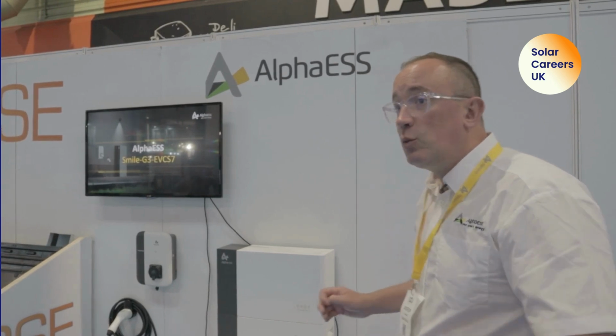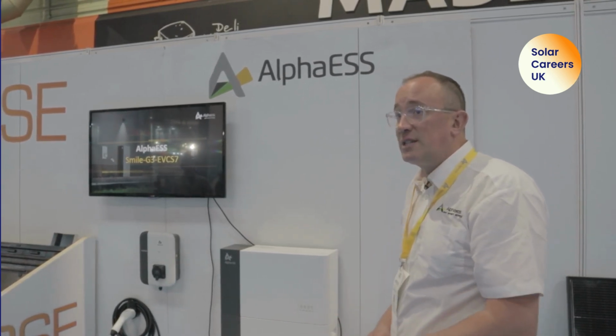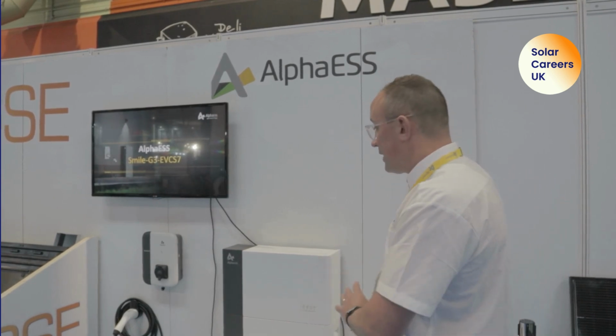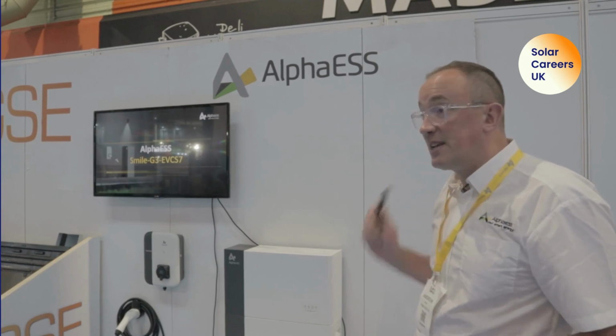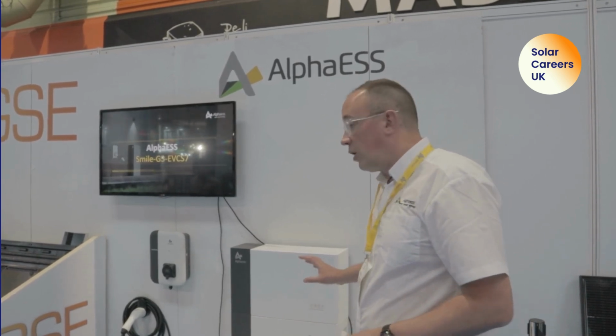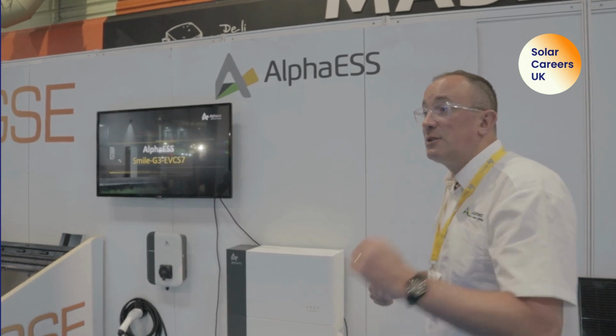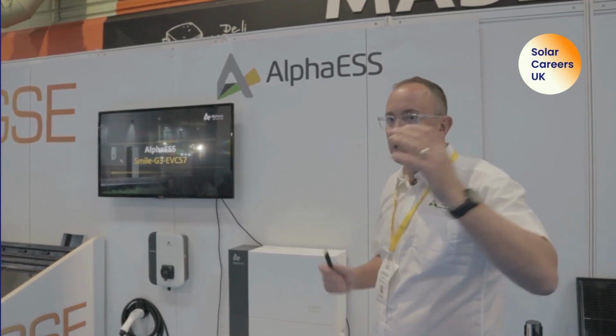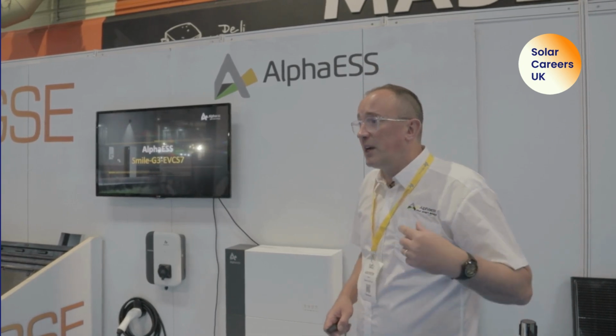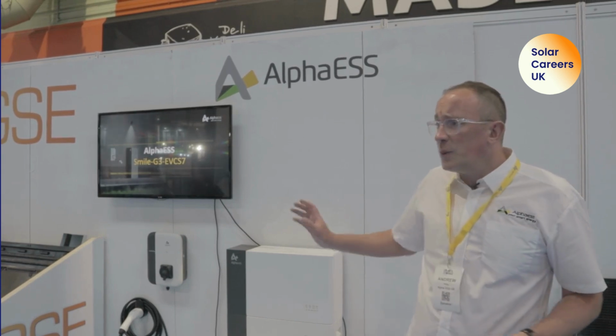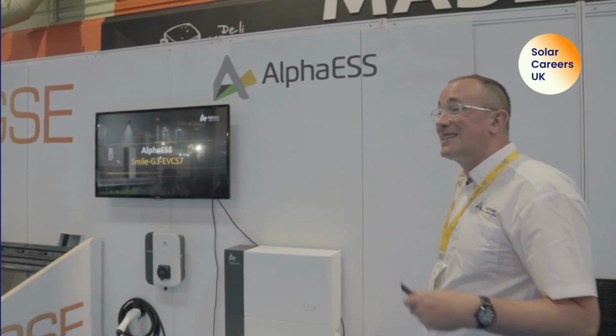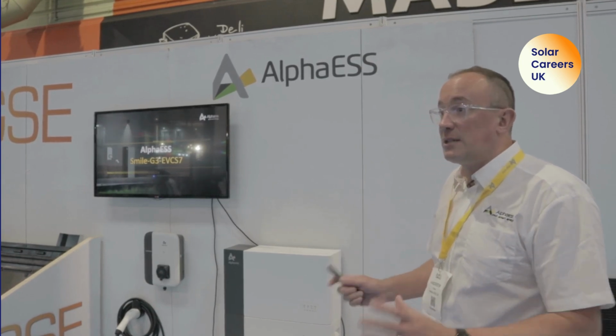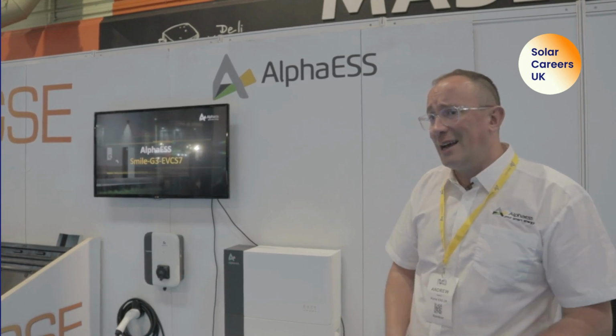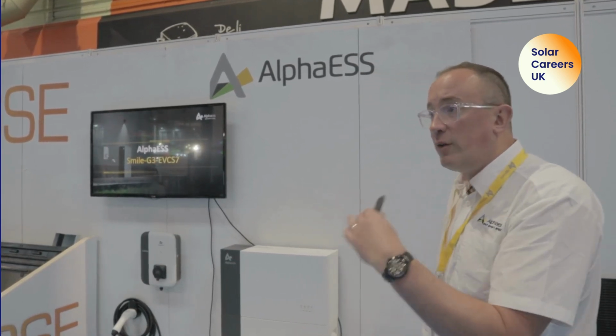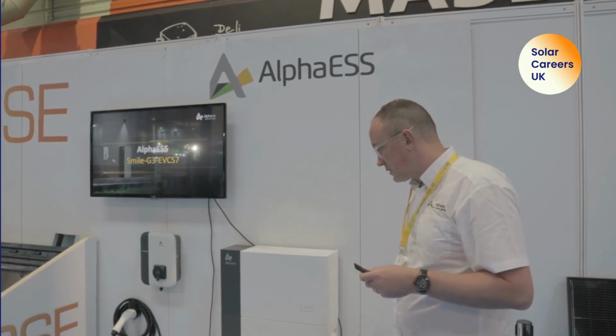With the 4 kilowatt hour battery, we can have up to 4 of those batteries, giving us a maximum of 16 kilowatt hours with that particular battery. It's lithium iron phosphate, same as pretty much everyone here, and it uses a high voltage battery scheme. The batteries themselves are 96 volts, and it's a series battery. So if we have 4, we have 4 times 96 at the inverter, so that conversion process is really efficient. We do have another battery module we can use with the system: a 10 kilowatt hour battery, a 10.1, and that's a parallel battery, so we can have multiple of those. Again, that's a 96 volt battery operating on that higher voltage battery cell.